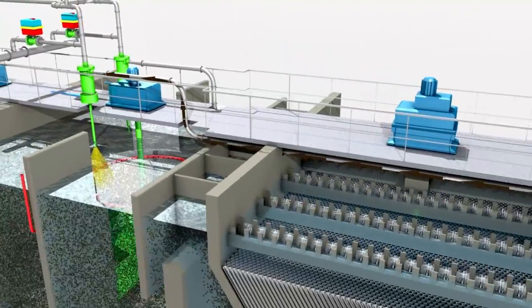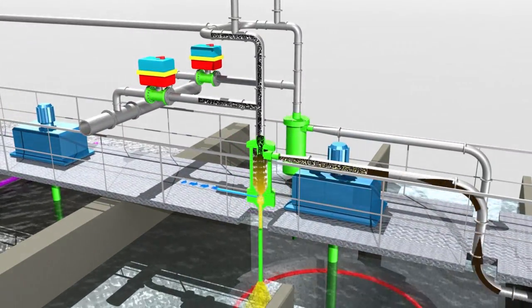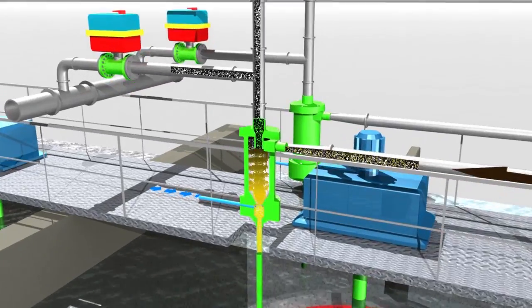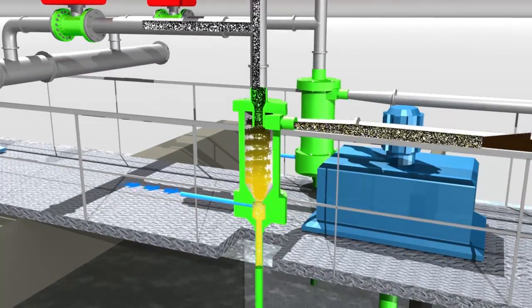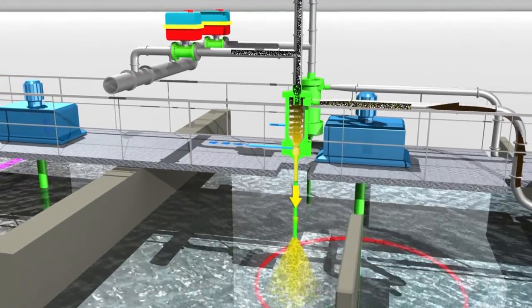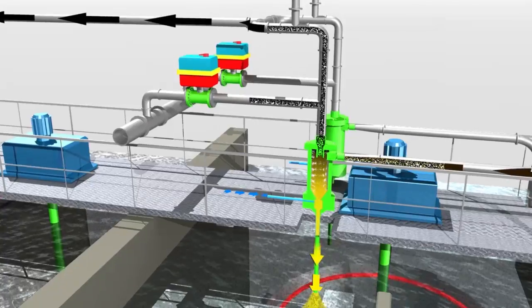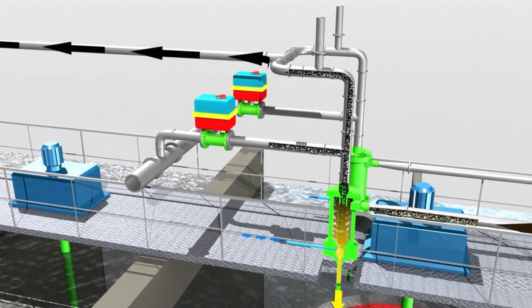a hydrocyclone. Pumping energy is converted into centrifugal forces, causing the light activated carbon to separate from the heavy microsand. The microsand is recovered at the cyclone underflow and re-injected into the flocculation tank, whereas the activated carbon exits the cyclone at its overflow.